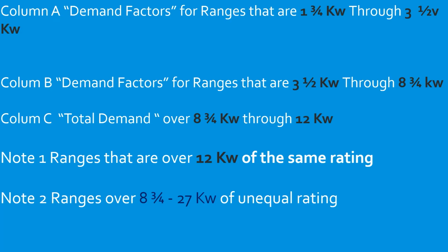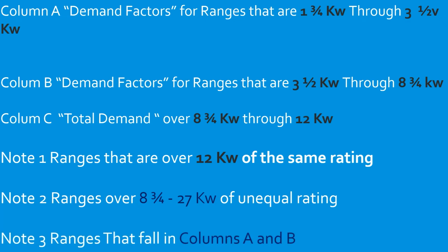So that's if we had a 12 kW range, a 13 kW range, and a 15 kW range. What do we do with all those and how do we get a demand? Well, I'm going to teach you exactly how to do that shortly. And then note 3 reiterates that we're allowed to use column A and column B for calculating ranges that fall in that section. So when you read that note, it says in lieu of using column C, you can use columns A and B.